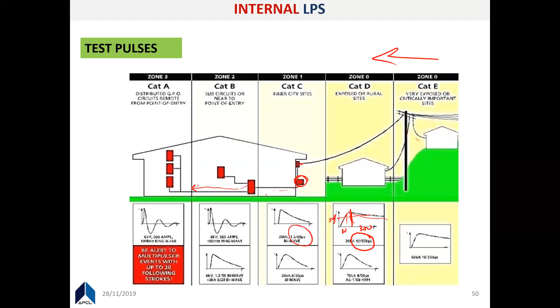Let's say there's an external DB here, and it's distributed into our internal areas. So according to the zone categorization, it's coming in, and you can see the waveform is 10/350 - it's a huge amount of energy, because 10 is here and 350 is where you have this 50% drop of the waveform. You can understand how huge the energy coming from this surge is, attenuating all along our path, the energy lessening. So you can install these SPDs according to these waveform characteristics - that's the concept and selection of SPDs.